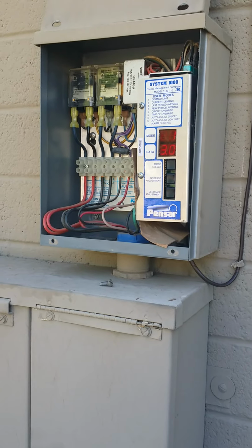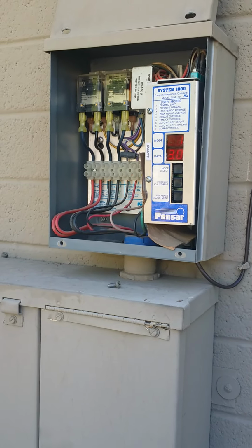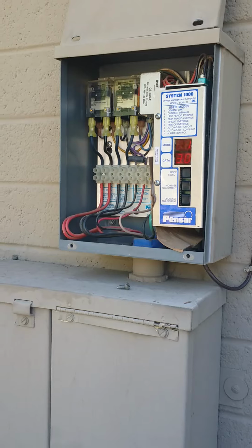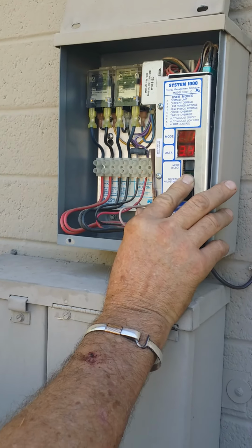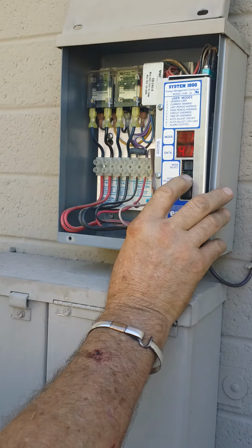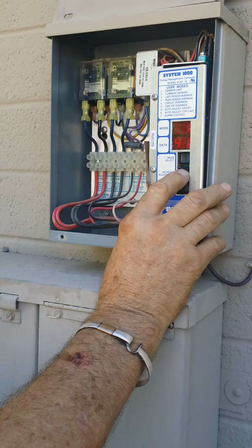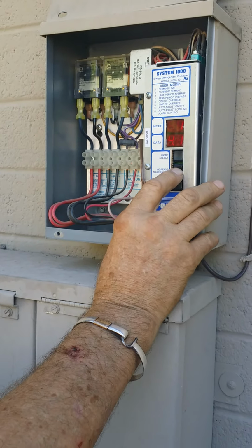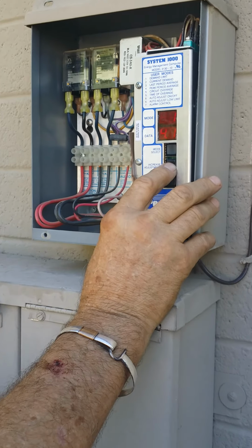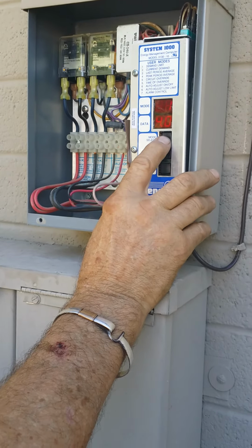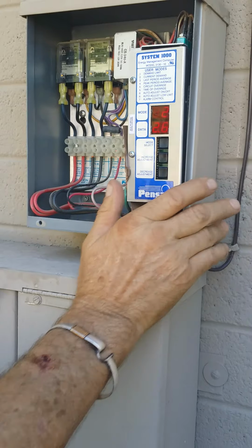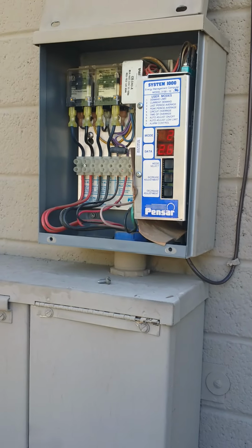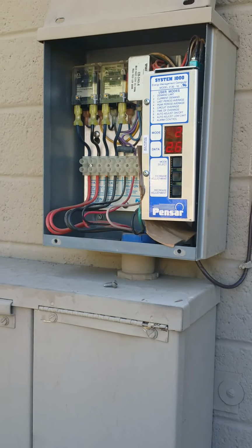7 may even be high for this. As efficient as the house is, 7 may even be high. We'll probably turn it down to 5 or 6 right now. In fact, we'll do that. We're going to set it at 5 kW. Because you're at 2 right now, I can set it even lower if you want, because you only use 2,000 watts at this point. Set it at 4. I'll set it at 4. Right now using 2.6. So now the kW is set at 4,000 watts. That's the maximum this house can use right now.